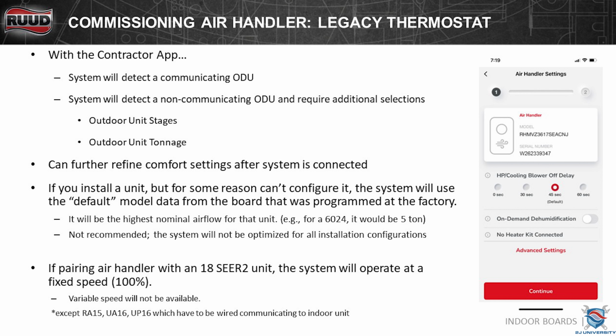So you're pairing a unit with the new RA15, UA16, or UP16. It's a 4-wire connection from the outdoor to the indoor unit. There's no longer any 24-volt connectivity. Those are all inverter units, and they have to have 4-wire from the indoor to the outdoor, which means you have to have a furnace on the indoor that will allow you to hook that 4-wire Econet connectivity to it.